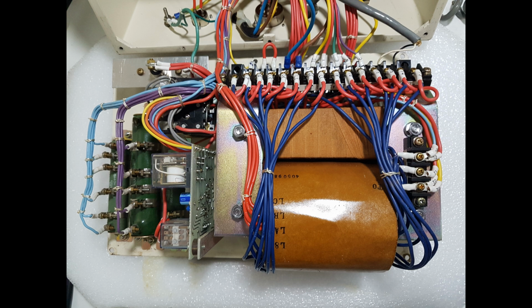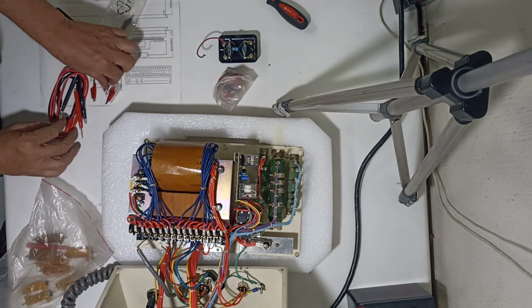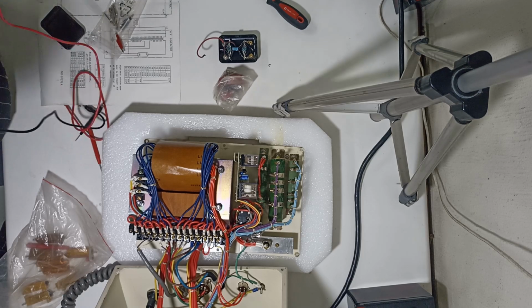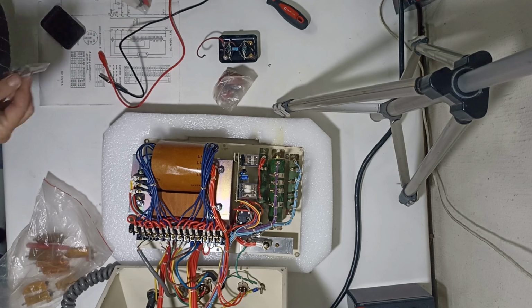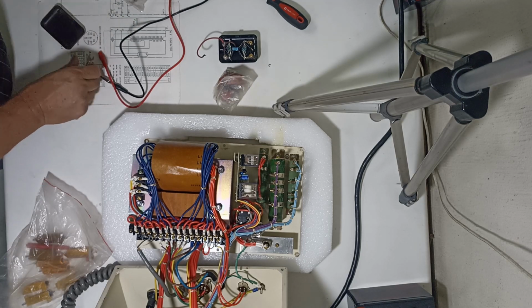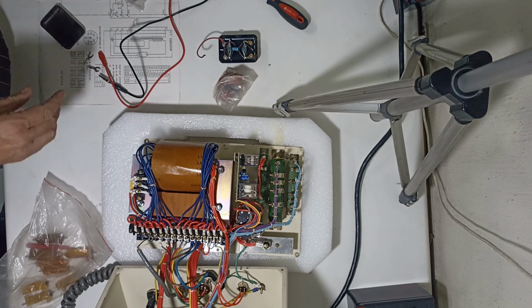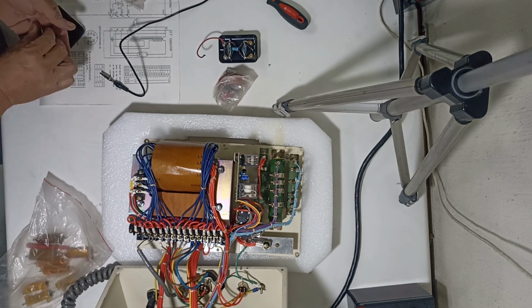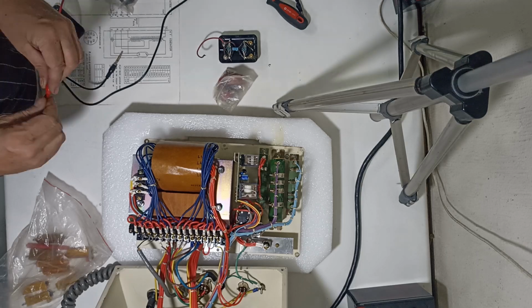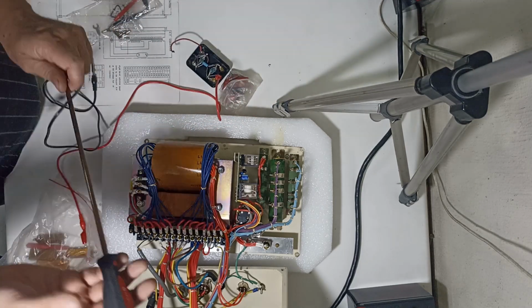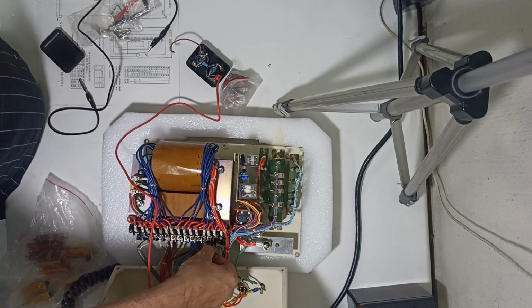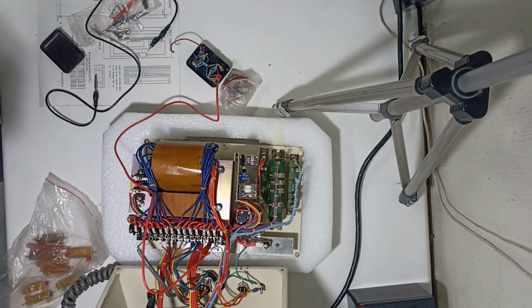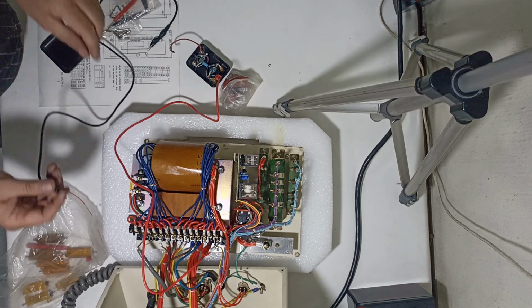This unit was brought to us for service and calibration. So let's take it apart, connect some test equipment and see what happens. First I will prepare the test equipment. I will remove the jumper in the center tap and connect my little resistor network on there. The resistor is a 10 ohm 2% tolerance resistor. This will connect to the oscilloscope, so every time I take an X-ray I will see the waveform or the pulses for each exposure on the oscilloscope. This will allow me to test and confirm and adjust the mA of this unit.